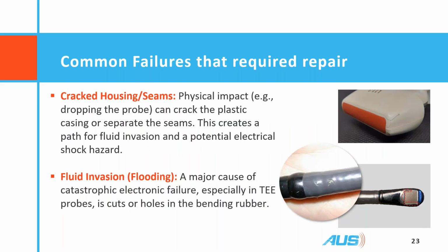As soon as you see damage like what we're showing in the picture, get that probe removed from service and evaluated. Again, the sooner the detection, the better.